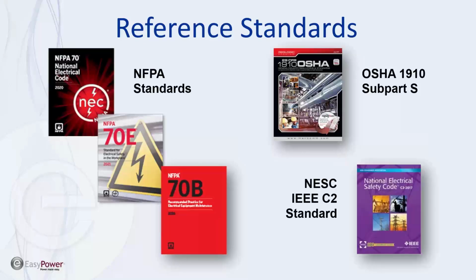The National Electric Safety Code is more of a medium voltage kind of guideline, so that's a utility guideline or utility-like work. So if you have 4160 volts and higher in your facilities, that's where you're going to want to go to make sure you're in compliance with things that are not, again, in OSHA. There is a lot more detail in the National Electric Safety Code than there is in OSHA, but that's also a guideline that was used for the electrical standards, more for the utility type of work.